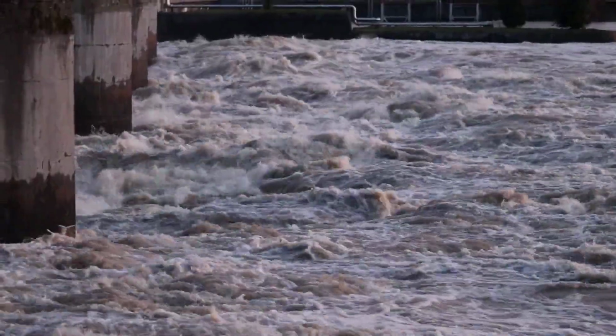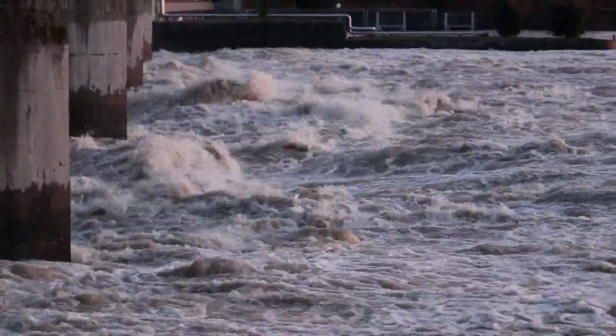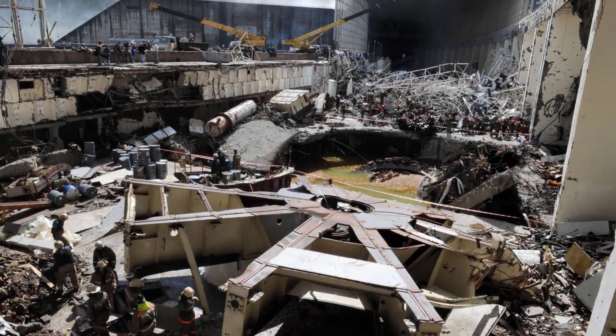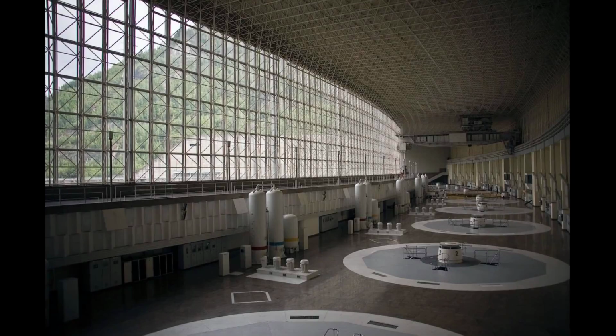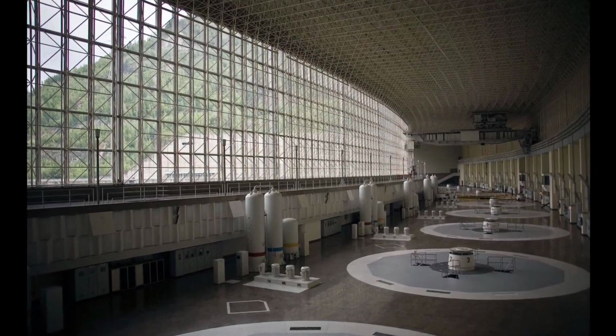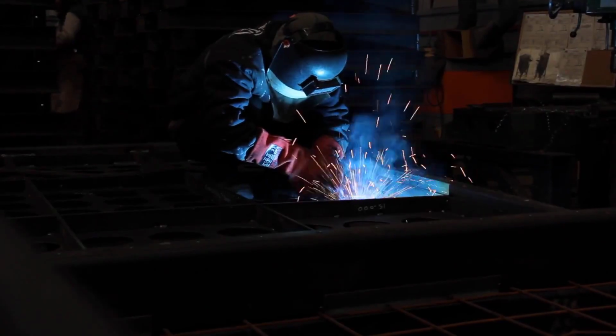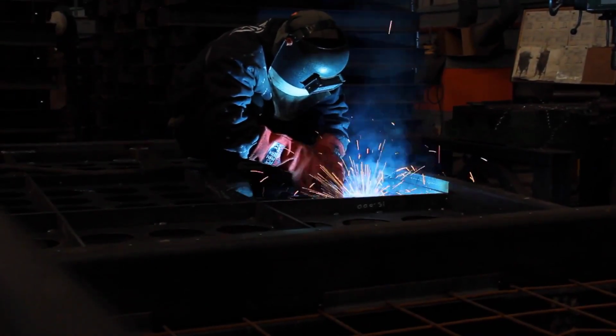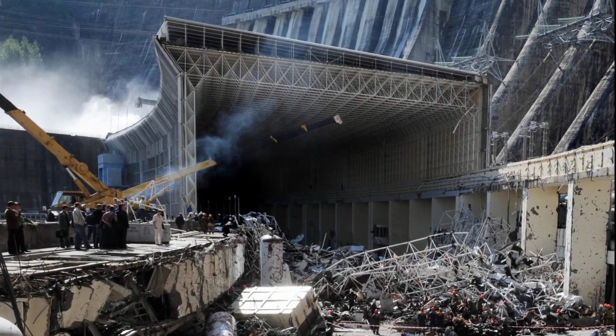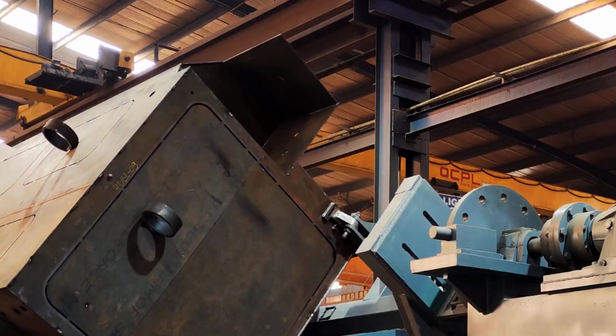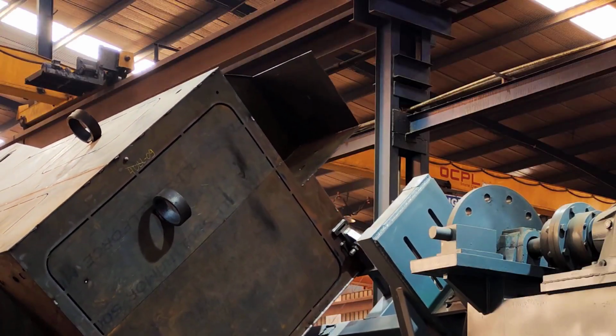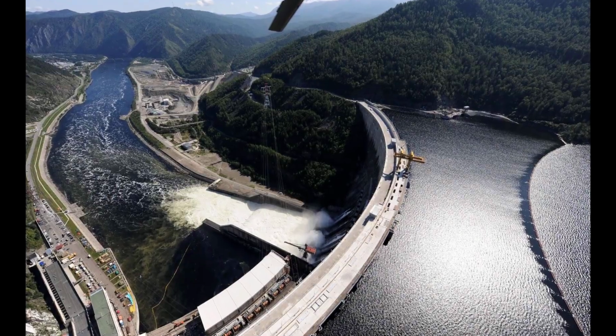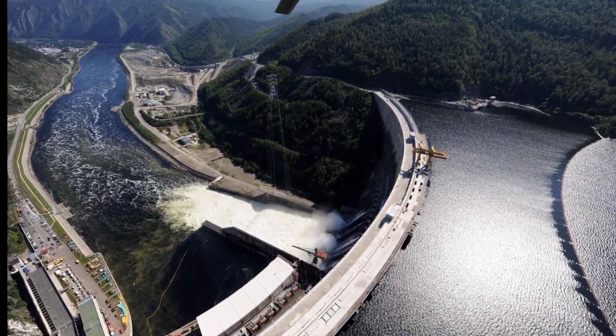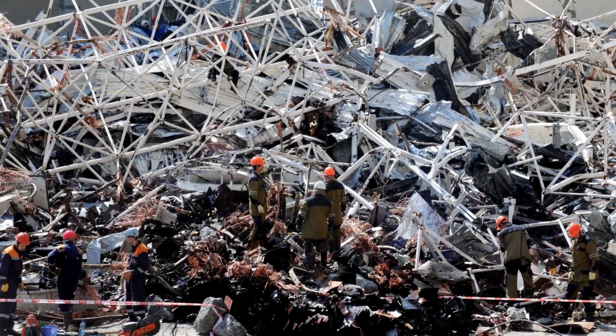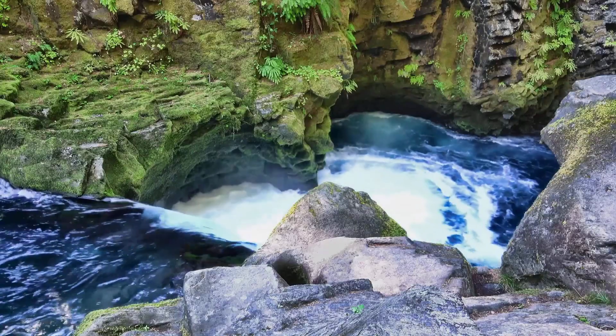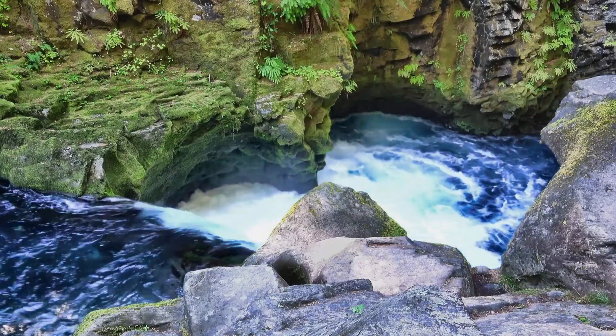What happens next takes about 20 seconds. With the fastenings gone, the pressure under the head cover did exactly what physics requires. 200 meters of waterhead, about 20 bar, lifted the cover, the shaft, the runner, and the 920-ton rotor vertically out of the seat, still turning. The rotor rose through the generator floor, tore itself apart against the structure, and came down across the hall. Behind it, the spiral case was now an open pipe pointing at the ceiling.